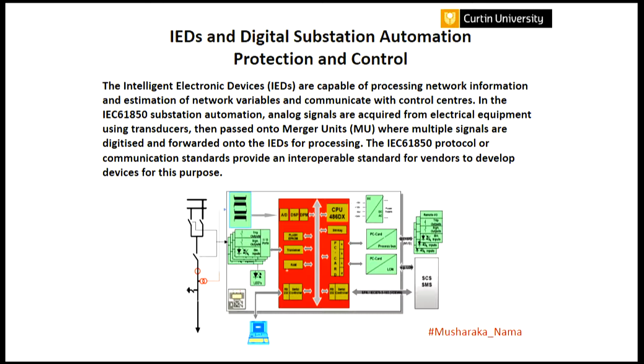To study this, our university set up an IEC 61850 laboratory that emulates a digital substation and its protocol. It includes 29 different IEDs from about 12 different manufacturers, like GE, Siemens, and others, so we can study the interoperability between different companies. This is very important for utilities, because if you buy GE equipment today and want to buy Siemens tomorrow, you can't if GE doesn't talk to Siemens. You don't want that situation, so we can demonstrate that interoperability in our laboratory.